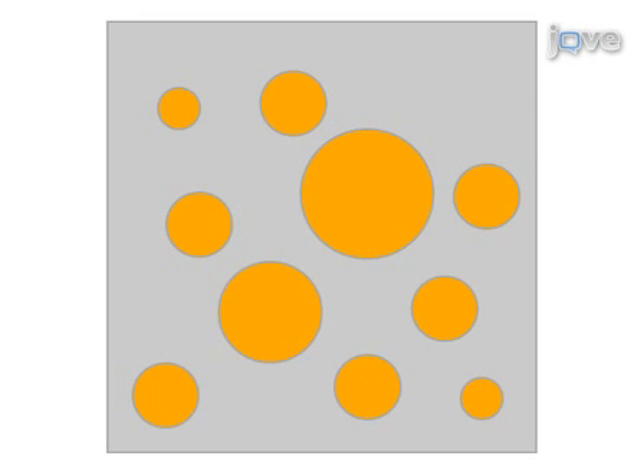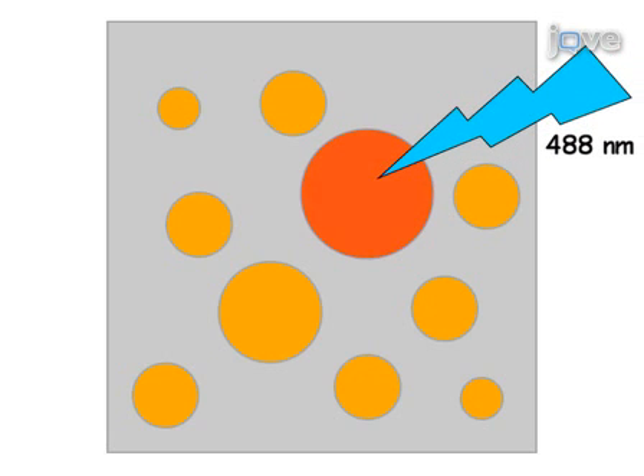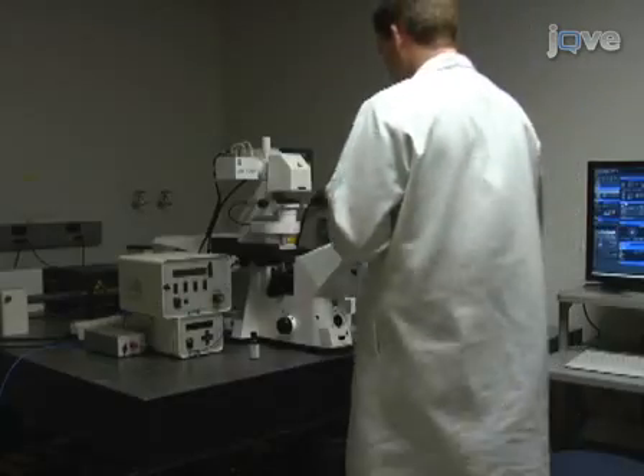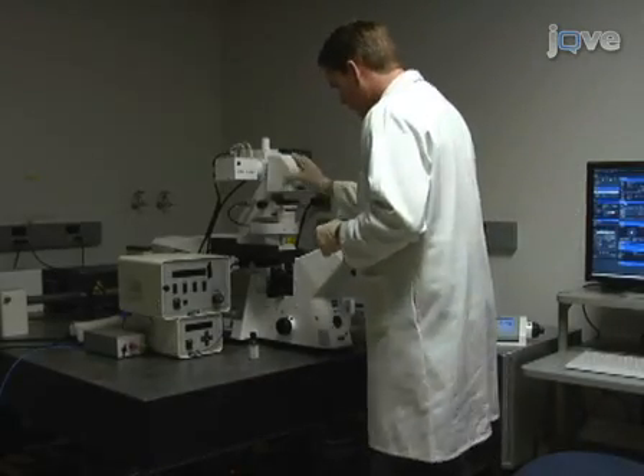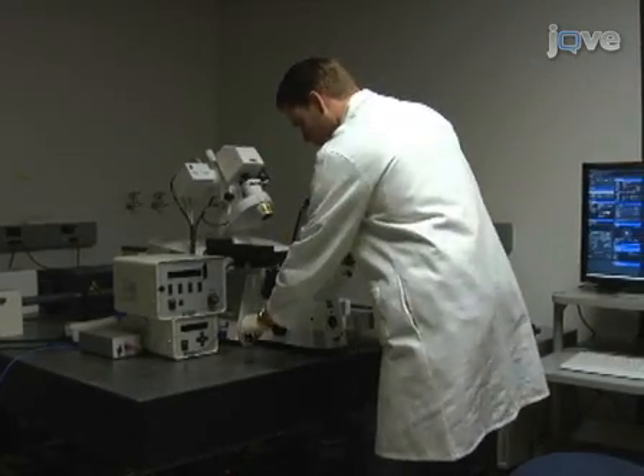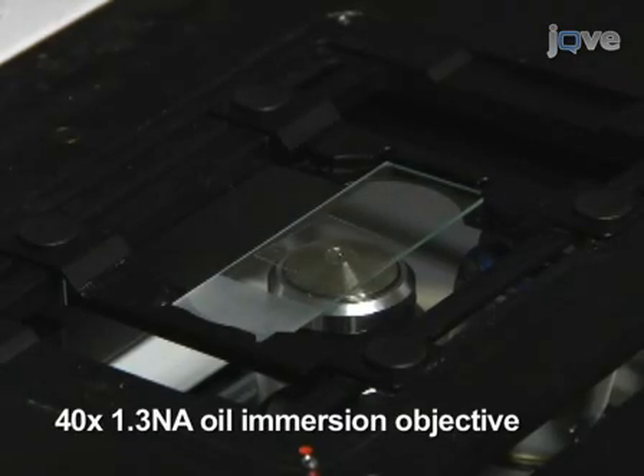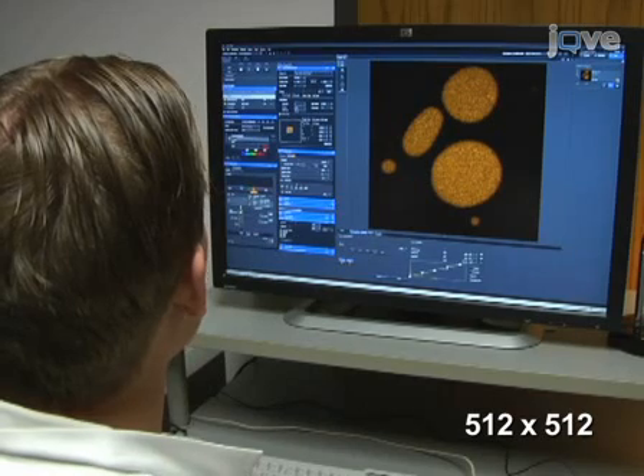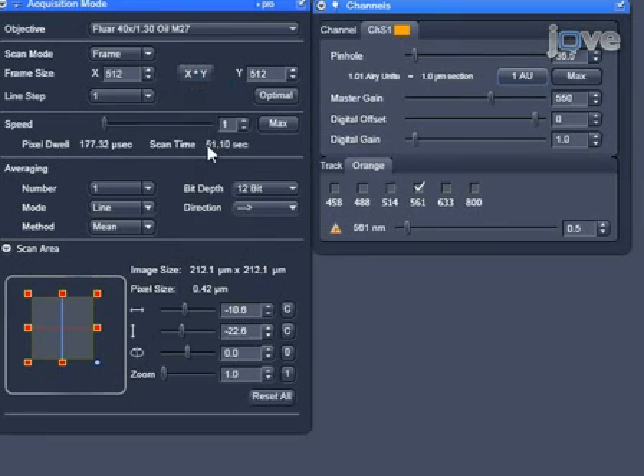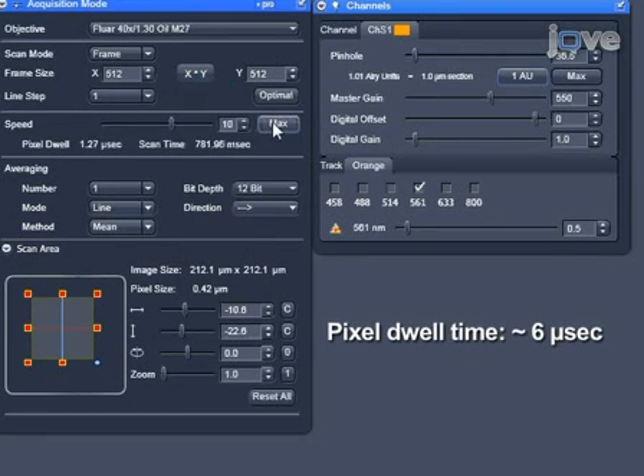The following procedure is a general strategy for setting up a fluorescent protein photoconversion experiment on a confocal laser scanning microscope. This procedure can be applied for purified proteins as well as for live cells. In this experiment, a droplet sample containing purified mOrange2 protein is used. As a general starting point for the photoconversion experiment, set up the confocal laser scanning microscope as follows. Use a 40x 1.3 numerical aperture oil immersion objective and an image size of 512 by 512 pixels. Set pixel dwell time to 6 microseconds.